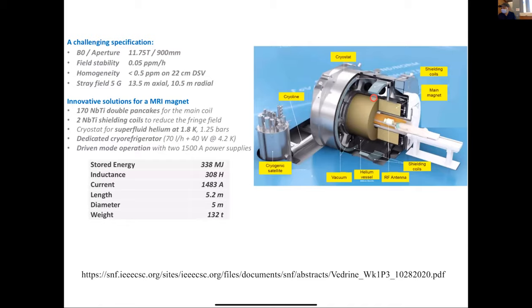The 11.7 T system stores over 300 megajoules of energy and has 1,500 amps of current running through it. Importantly, it is the first whole-body 11.7 T system — previous seven-Tesla systems could only fit a head, but this one can accommodate the full body.